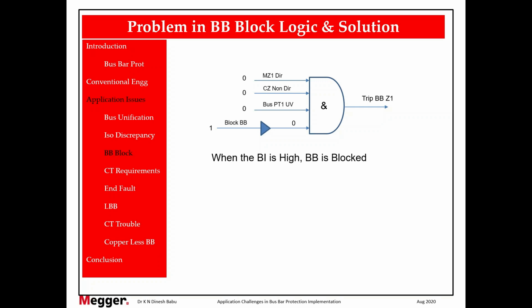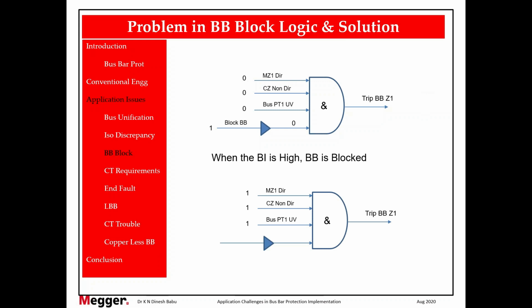So what happened? In some substations we faced this problem. There we blocked this bus bar, and then we disconnected the CT secondary, and we were injecting from the test kit, and now the main zone is picked up, check zone is picked up. We have simulated bus PT under voltage condition, so all are 1, but the relay is not tripped because this is blocking. Now during the scenario, there was a disturbance in the DC supply, battery disturbance, due to which the relay rebooted. After the relay rebooted, bus bar tripped.